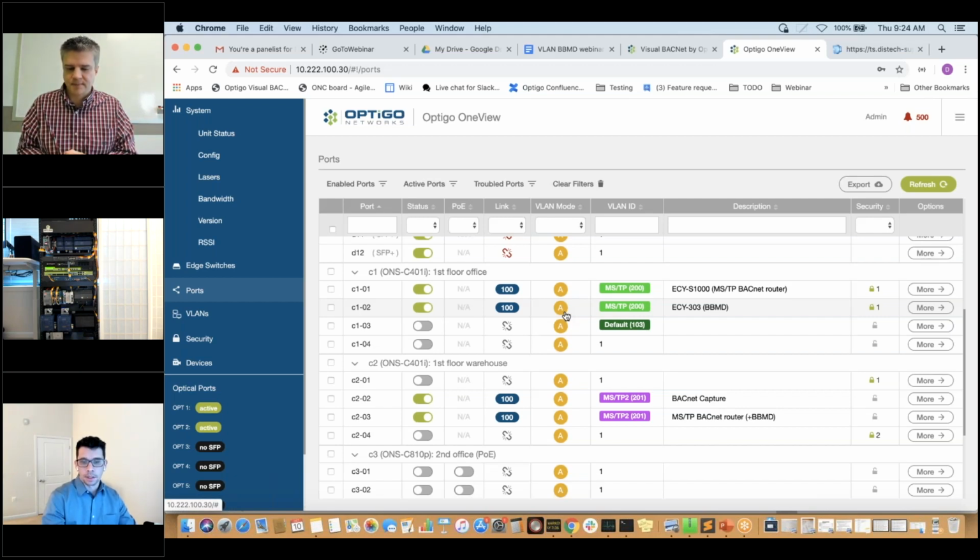And just to add on to this question, this is a good question, because when you're designing a site, if you're going to daisy chain a bunch of controllers, and you're looking at cost-wise what it costs to daisy chain those controllers, you're trying to daisy chain as many as you can to save money and use fewer ports on your switch. But just keep in mind, you can assign a VLAN per port, but everything daisy chained on that port is now on that VLAN, everything. So when you're looking at how many devices to daisy chain on a port, keep in mind that if there are devices like an air handler or an RTU mixed in with VAVs, you may have a reason later to have an air handler on a separate VLAN. So you may want to bring down a separate run and give it a separate port.